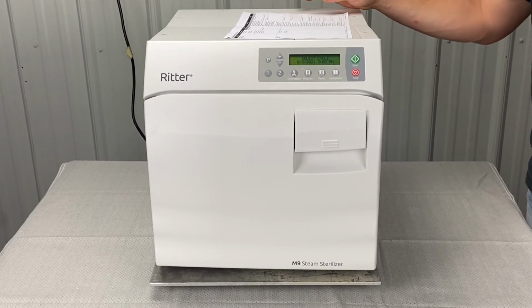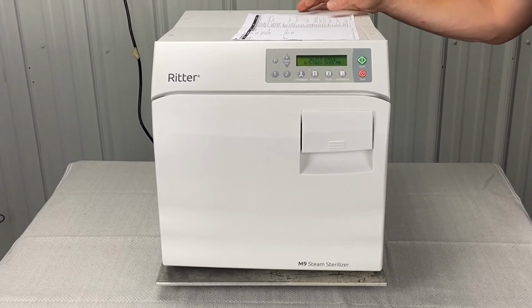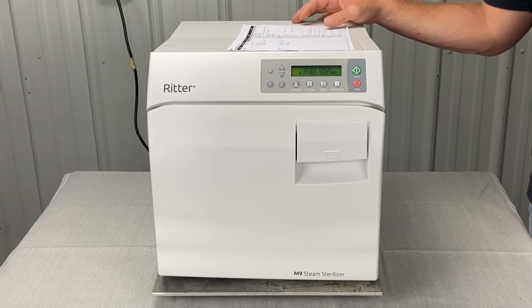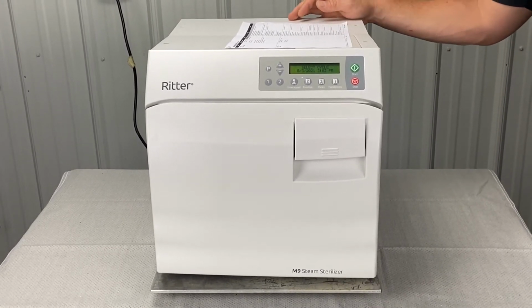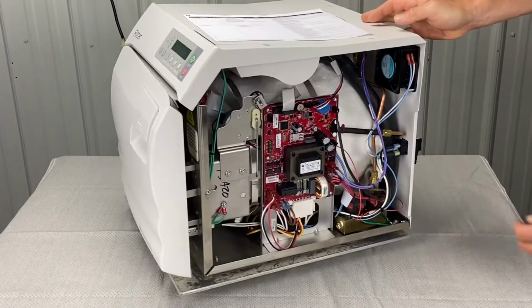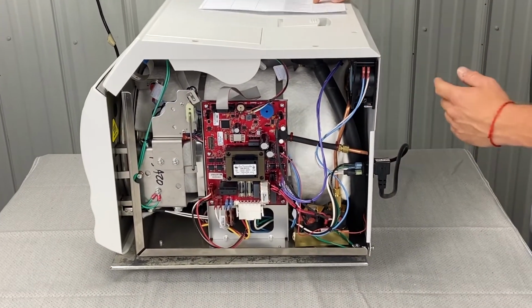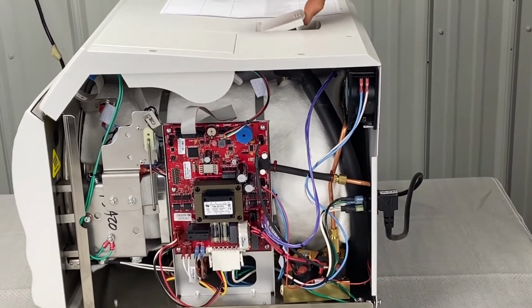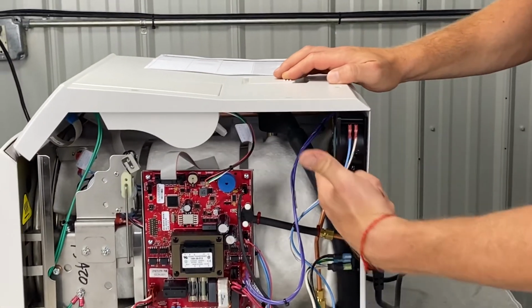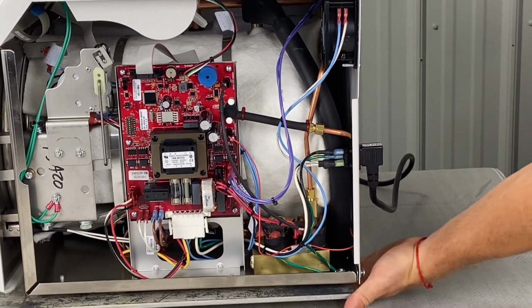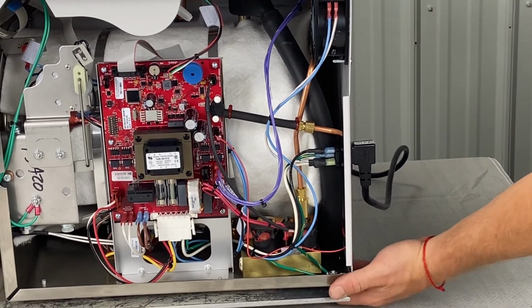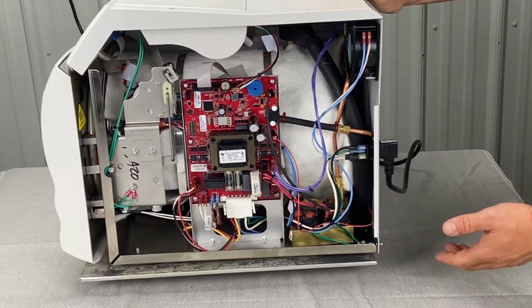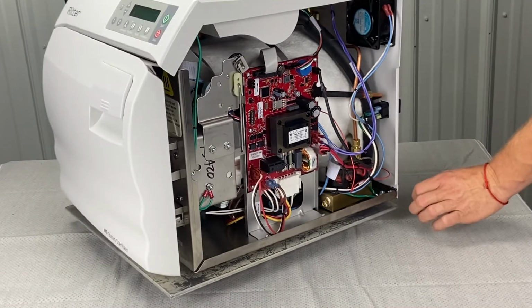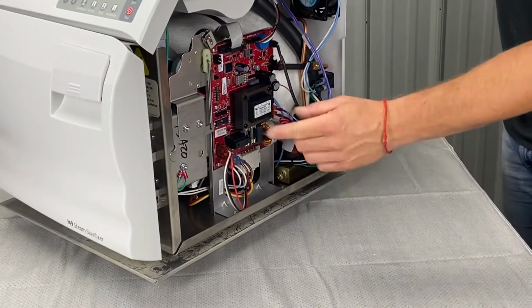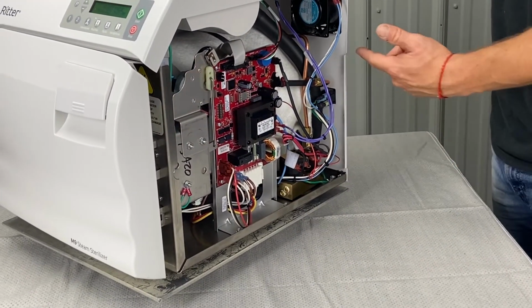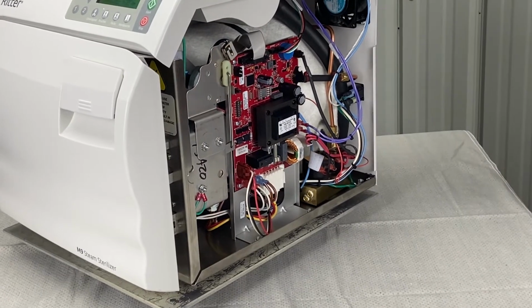Okay, so you're leaking or defective pressure relief valve. Check for water, steam leakage from beneath the rear of the sterilizer. Okay, so the pressure relief valve is under here. You can pull on it. That's how you engage the pressure relief valve. But there's a tube that it flows down here, and then underneath the bottom here, that's where it drains to. So if you are constantly seeing water in the back right-hand corner underneath the unit, or you're seeing it drip out the right side, it could be that your pressure relief valve is bad.